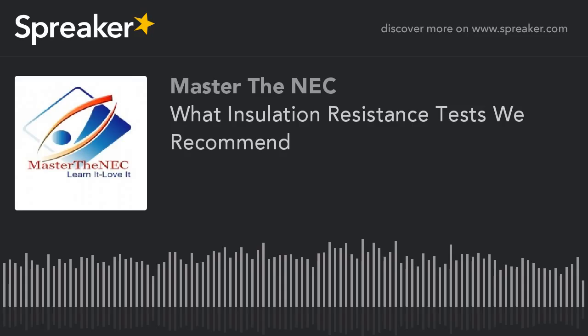Okay, so hopefully I've explained those tests. I went a little longer on this podcast than I wanted to go. We recommend the 60-second spot test, and the majority of the time I recommend the polarization index test, which is a 10-minute and a 1-minute test, all consecutively.